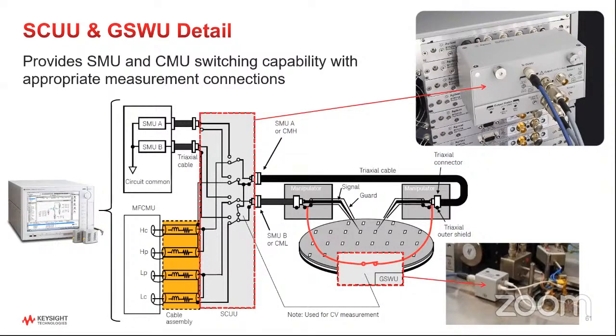Typically, it's called the guard switch unit. You can see it in the bottom right there. What it basically does is it shorts out the guards together when you're making a capacitance measurement and leaves them open when you're making an IV measurement. I'm not going to go into all the details, but if you do that, it will give you better capacitance measurement results than if you don't. And of course, you don't want them shorted together when you're making an IV measurement because they're going to be at different voltages. But it does this for you automatically, and again, it's something where you don't have to think about it.